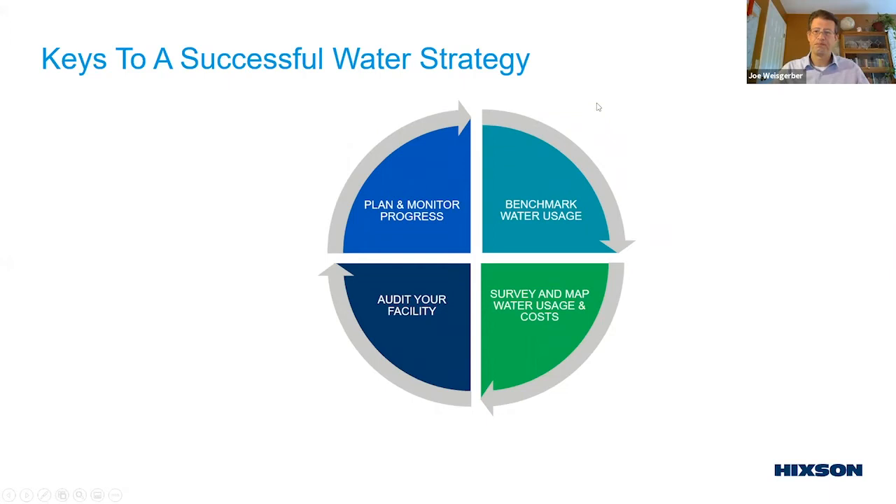Hixson has been implementing a water management program for quite a few years. When Warren joined in 2002, Hixson had already established a 'waste buster' program. Working with clients to reduce waste to the POTW, they branched off and developed a parallel water reduction program. The model on screen is a Plan-Do-Check-Act or PDCA cycle adapted for water and waste minimization. It begins with benchmarking water usage, then surveying where water is used and what those costs are, followed by auditing the facility, and finally taking action by developing a plan and monitoring progress.